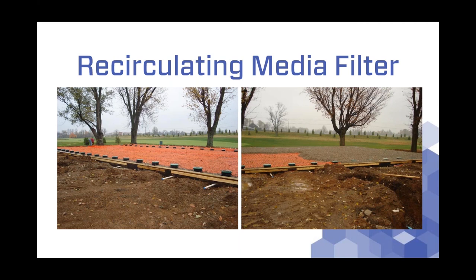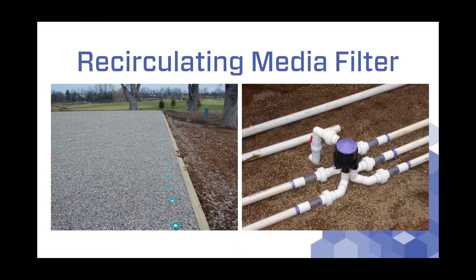On the left side, you'll see the finished product — all the gravel's in, a couple of different kinds of cleanouts so we can do maintenance, adjust pressure heads, etc. Nothing is installed over the top of the final gravel, and we get that question quite a bit. Do you cover it with mulch? Do you plant plants in it? The answer to all those is no. We want that gravel to remain open for oxygen transfer. Any weeds that grow in there will be picked out by the contractor, and we'll get a final grade up to the wood framing with grass planted around the outside.